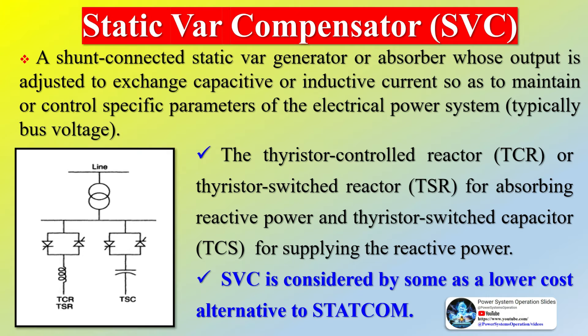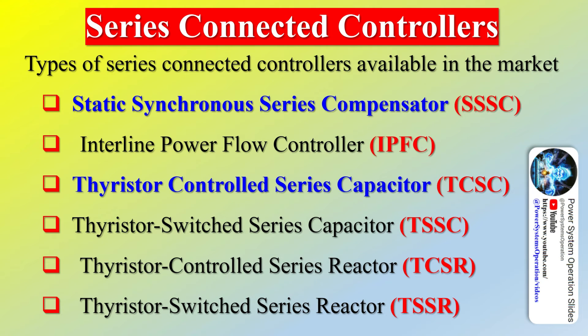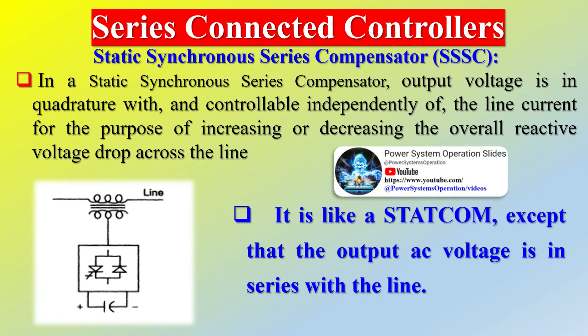Basic types of FACTS controllers are: series controllers, shunt controllers, combined series-series controllers, and combined series-shunt controllers. Series controllers could be a variable impedance — capacitor, reactor, etc. — or a power electronic-based variable source of main frequency, subsynchronous and harmonic frequencies. They inject voltage in series with the line. If the voltage is in phase quadrature with the current, the controller supplies or consumes reactive power; any other phase involves control of both active and reactive power.